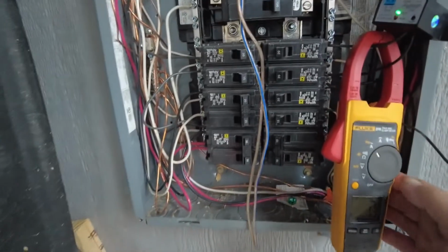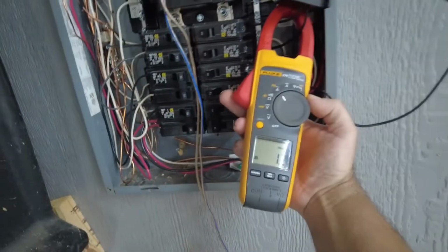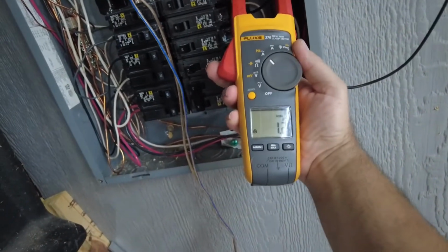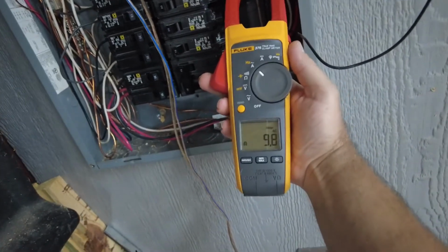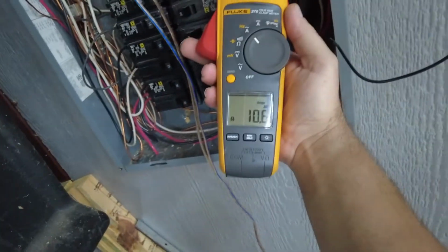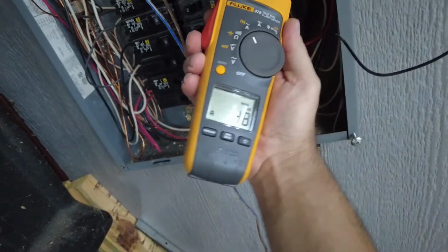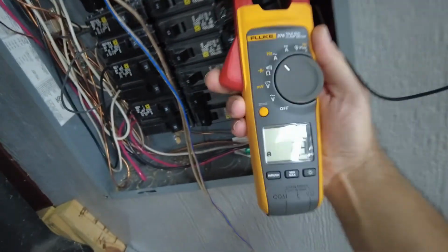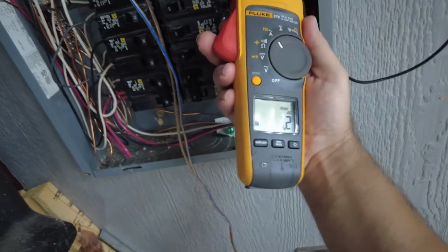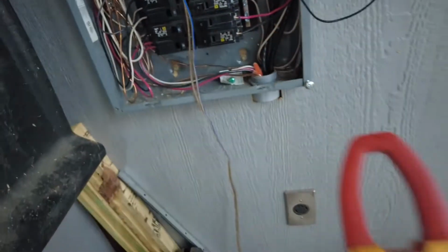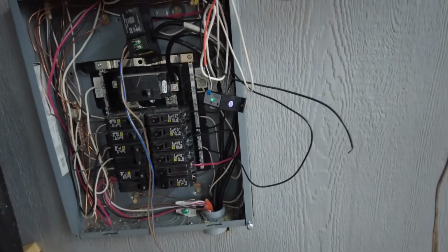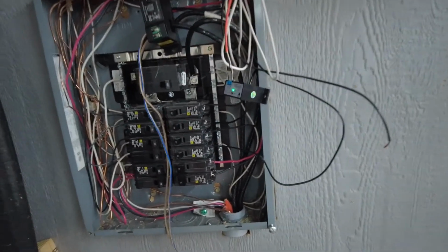And maybe what I should have shown was, here's the Fluke. That's around both of them wires. It's showing 1.2. If I go around one, it's showing 9.8 and 10.6 if you go around individual wires, but if you go around both, it's only showing 1.3. So once again, I just want to demonstrate that. Not everybody knows that, so keep that in mind if you're going to be using some sort of limiting device on your inverters.